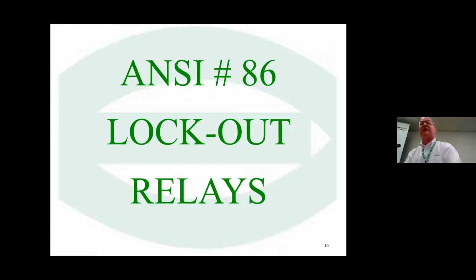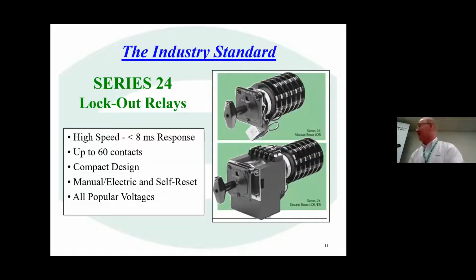The next Series 24 device is most commonly referenced to the 86 Lockout Relay. And that 86 Lockout Relay gives you the highest speed control switch on the market at 8 milliseconds for a manually operated switch. Essentially what we did was go to utilities and ask them what they wanted in a lockout relay.